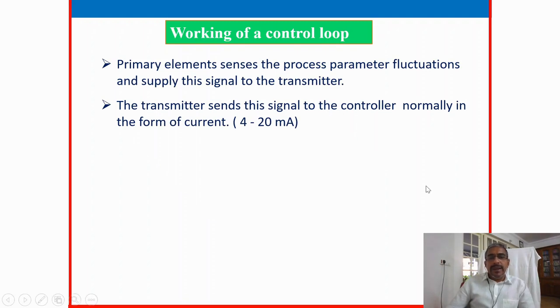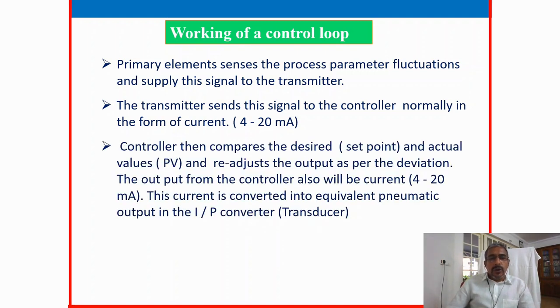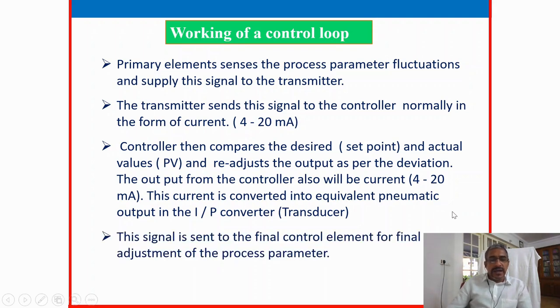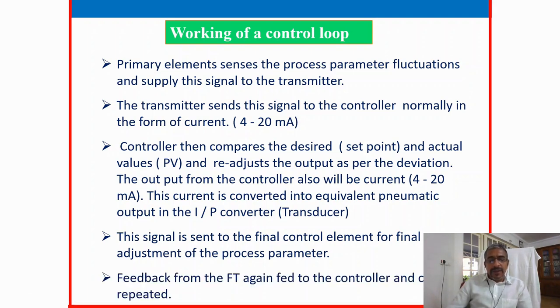Working of a control loop: the primary element senses the process parameter fluctuations and supplies the signal to the transmitter. The transmitter sends the signal to the controller, normally in the form of current 4 to 20 milliamps. The controller compares the desired set point and actual value and readjusts the output as per deviation. The output from the controller — also 4 to 20 milliamps — is converted to equivalent pneumatic output using an I/P converter (current to pneumatic converter or transducer). The signal is sent to the final control element for final adjustment. Feedback from the flow transmitter is again fed to the controller and the cycle repeats.